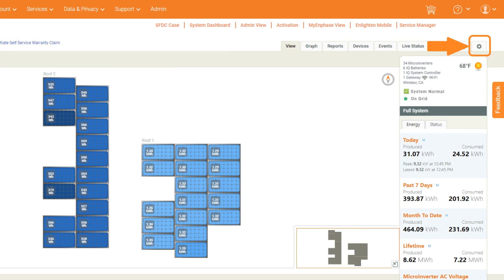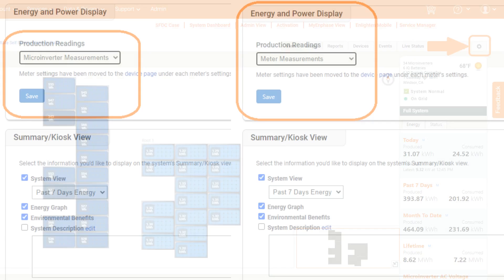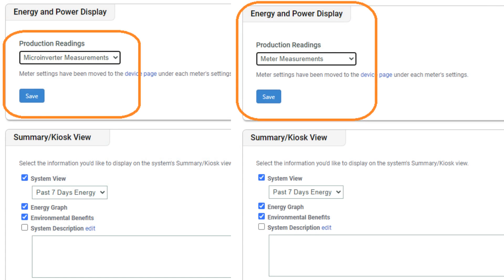If we are not capturing production correctly and need to change the energy and power display, you will need to select the settings icon in the gray taskbar. Once you are in settings, scroll to the energy and power display option. If microinverter measurements are displayed in the production readings drop-down and you are using meters, change it to meter measurements and then click Save.